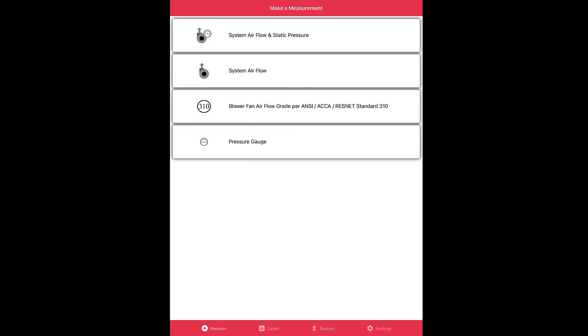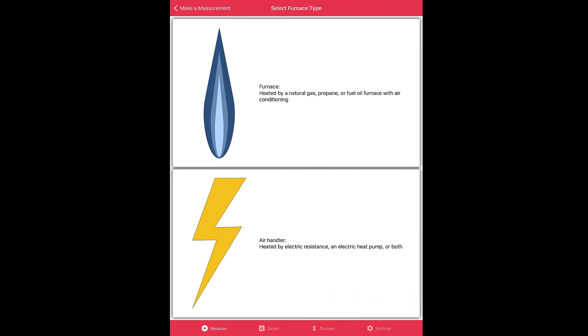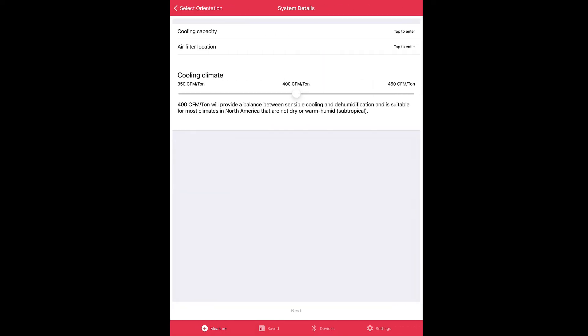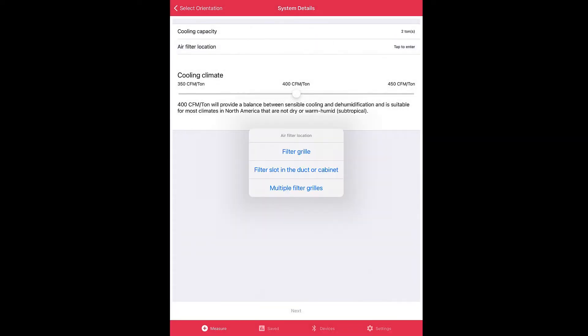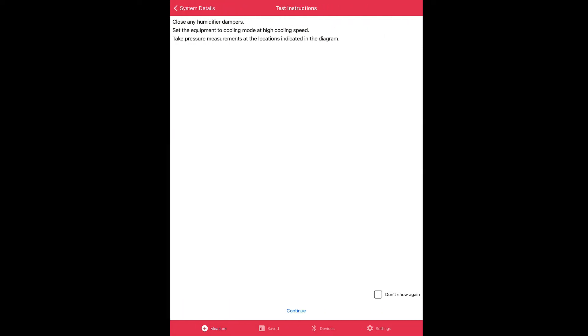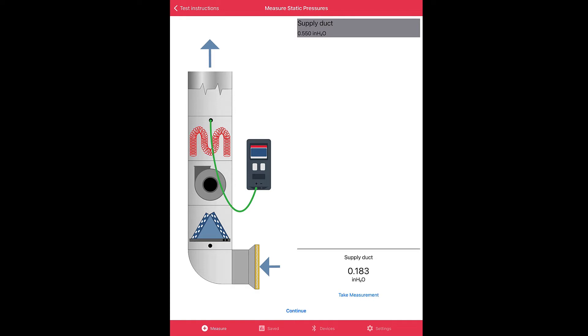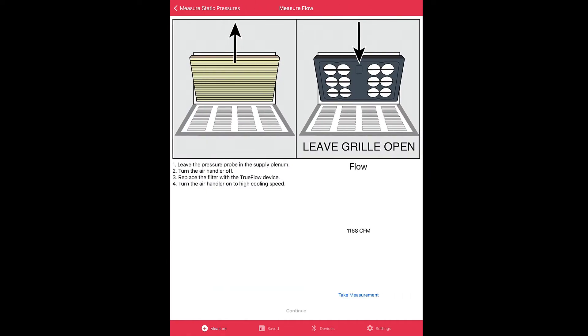Now I'm going to run through a quick workflow so you can see what I mean. Let's select system airflow, air handler upflow, cooling capacity of a two-ton, air filter location filter grill, and let's leave it at 400 CFM per ton. Click next. Now test instructions—let's click continue. All right, here we are. We've got a pressure gauge reading pressure in the supply plenum. Now let's take measurement and let's click continue.